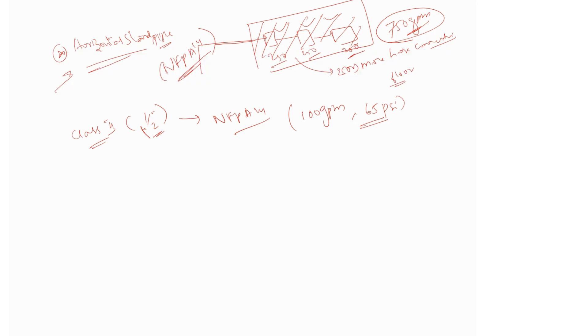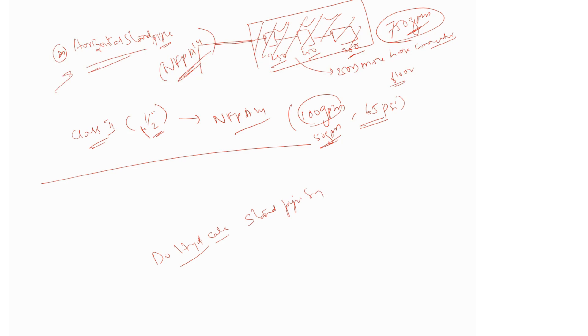One more point related to the Class 2 system: since Class 2 systems, as already told, use 1.5-inch hose valves, as per NFPA 14 we need to have about 100 GPM — or it could be 50 GPM — and the pressure requirement at the remotest hose or hose cabinet will be 65 psi. So now what we are going to do is perform the hydraulic calculations for the standpipe system.